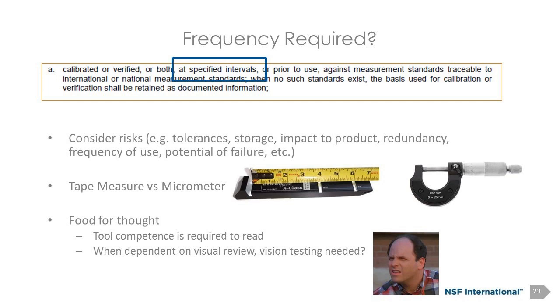And then I've been to businesses where, you know, a micrometer gets used once in a year, and they had a 3-year cycle on the micrometer. It's, again, up to you as long as you can demonstrate the tool is fit for the purpose it's being used for, and that it's capable of performing that measurement, and that it's still in good status, and when it's not in good status, the product impact is analyzed.